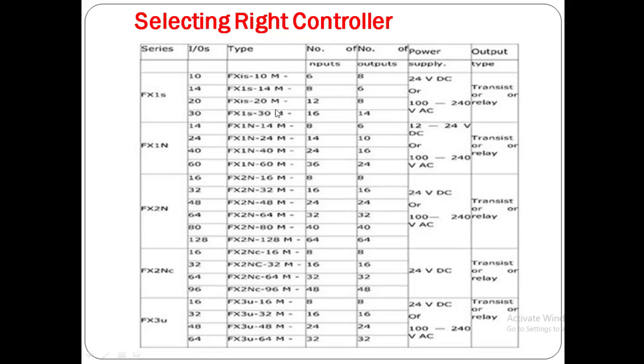FX1S 20M has 20 total I/O — 12 inputs and 8 outputs. FX1S 30M has 16 inputs and 14 outputs. In the FX1N series you can get from 14 to 60 input/outputs. In FX1S and FX1N, the FX1N 14M can get 12 to 24V DC input and 100 to 240V AC input, available in both transistor and relay type.